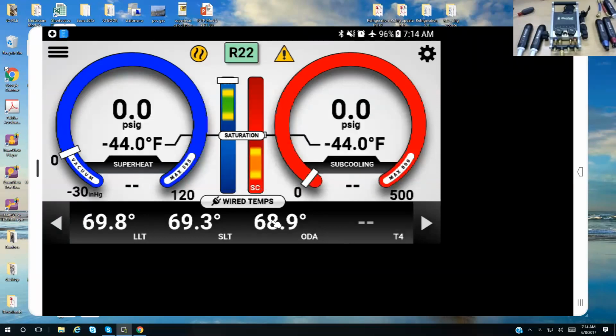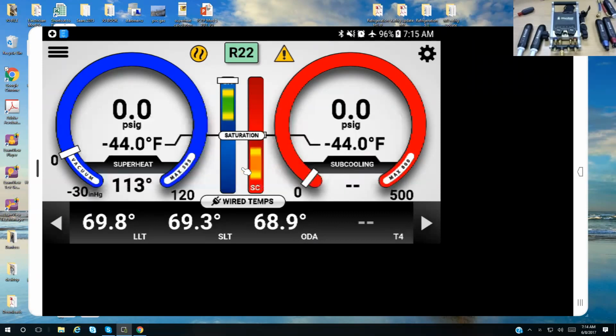And then the third one, the little air thermistor, we're going to leave as the outdoor air. We could add a fourth one if we wanted to be our discharge line or another ambient air, or however you wanted to configure it. But for this case, say I'm working with a residential split system heat pump or air conditioner, I'm going to set up suction line, liquid line, outdoor air. So we have our probes paired up. We have our thermometers in place.